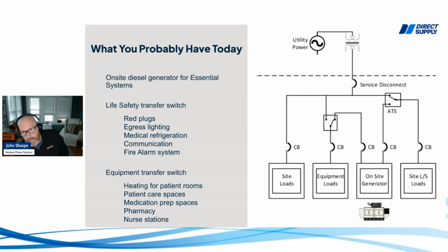Essential systems in this case covers both transfer switches - let me get that straight. So one, you have a life safety transfer switch, and as I mentioned, that's your red plugs, your egress lighting, medical refrigeration, communications, fire alarm. Those are all code required, so you need a generator to back those things up.